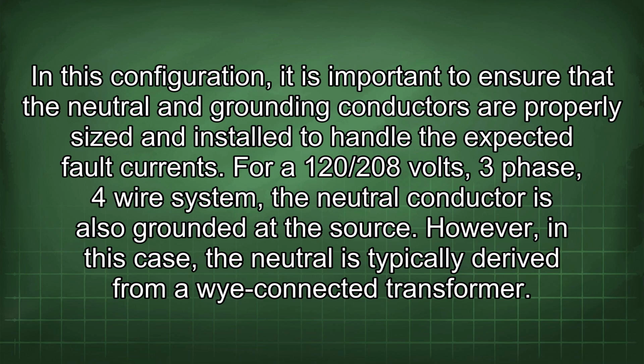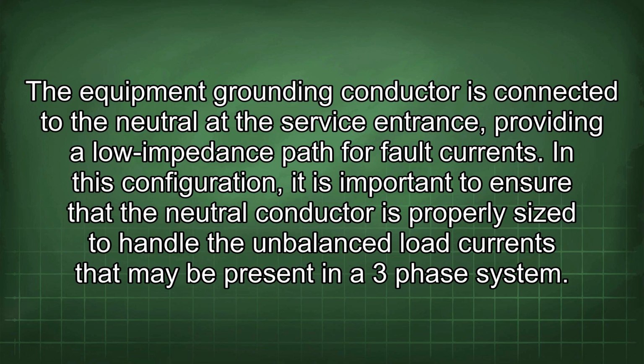For a 120/208 volts, 3-phase, 4-wire system, the neutral conductor is also grounded at the source. However, in this case, the neutral is typically derived from a Y-connected transformer. The equipment grounding conductor is connected to the neutral at the service entrance, providing a low impedance path for fault currents. In this configuration, it is important to ensure that the neutral conductor is properly sized to handle the unbalanced load currents that may be present in a 3-phase system.